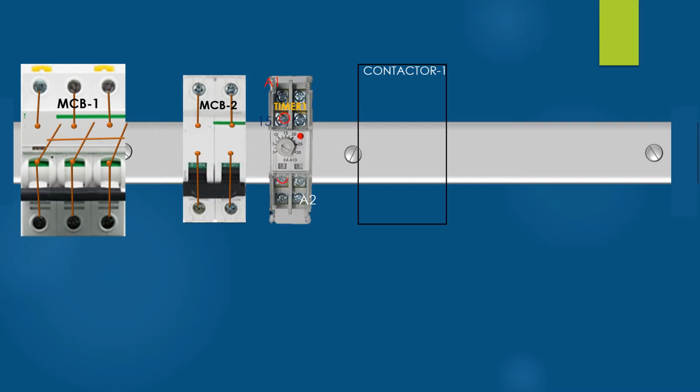It has two sets of contacts. On one side there are contact numbers 15, 16 and 18. On the other side the contacts are 25, 26, 28. Here, the contact between 15 and 16 is NC, normally closed, and between 15 and 18 is normally open, NO.